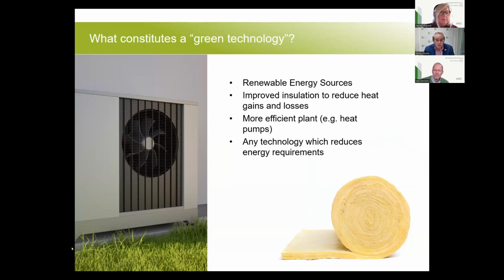Significant savings can be made by improving insulation values. It may seem obvious, but you'd be surprised what that can save, and it can be modelled quite accurately with modern software now. However, we need to be careful in Britain, with our mild summers and all this insulation and sealing up, that we don't end up with buildings that overheat regularly in summer. We're finding a lot of new flats don't cost much to heat, but are really difficult to cool down in summer. We need to model summertime overheating much more than we used to, and ensure there's enough ventilation in summer to through-ventilate those buildings.